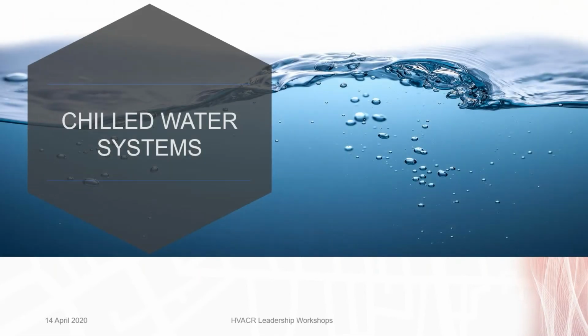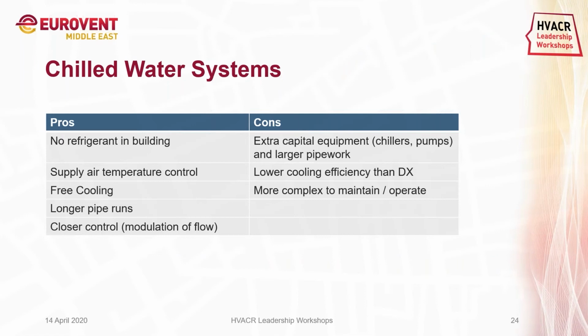Now coming to the chilled water system, as you know, a chilled water system has its own merits and demerits. The pros are: no refrigerant in the building, supply air temperature control, free cooling is possible, longer pipelines are possible, and closer control with modulation of the flow. And the cons are extra capital equipment. Of course, chillers and pumps are required for a chilled water system, and larger pipework is required. Lower cooling efficiency, that's due to the additional cooling medium and a further heat transfer. So it is more complex to maintain or operate.